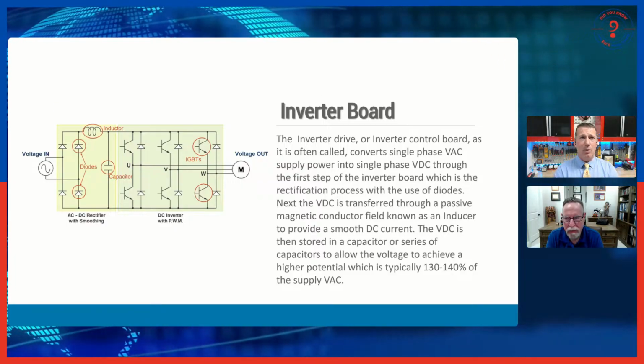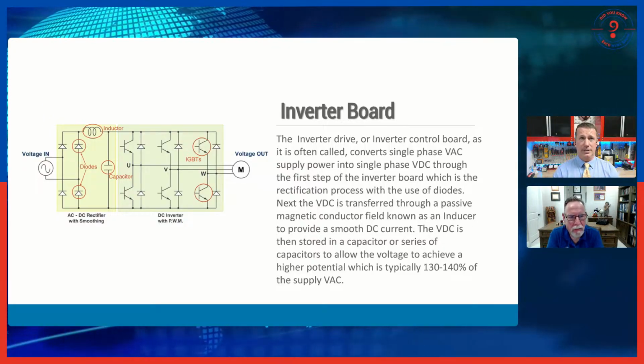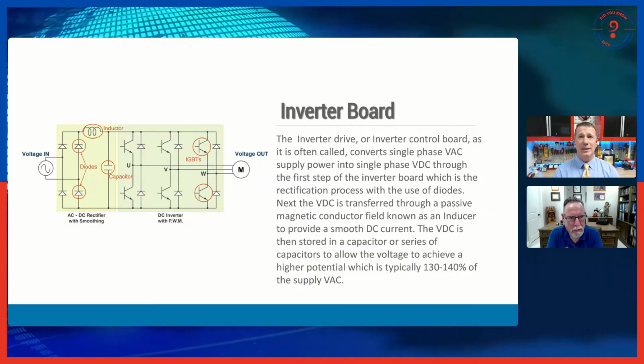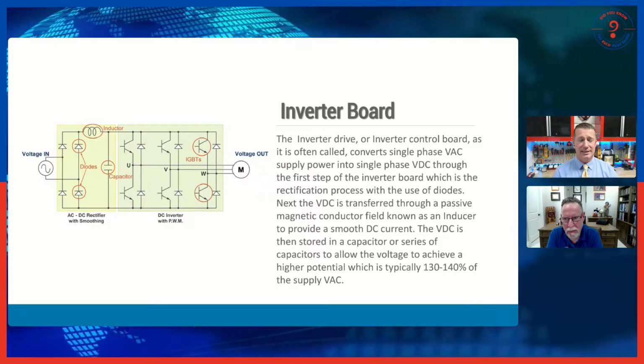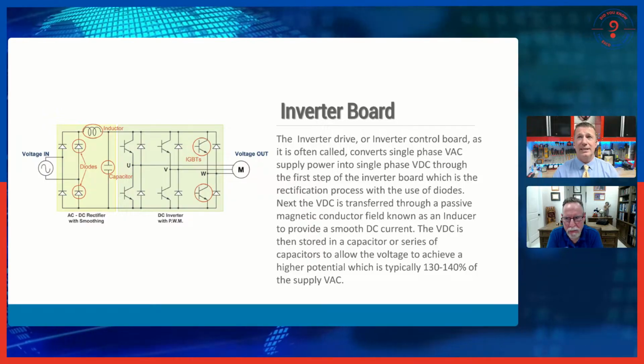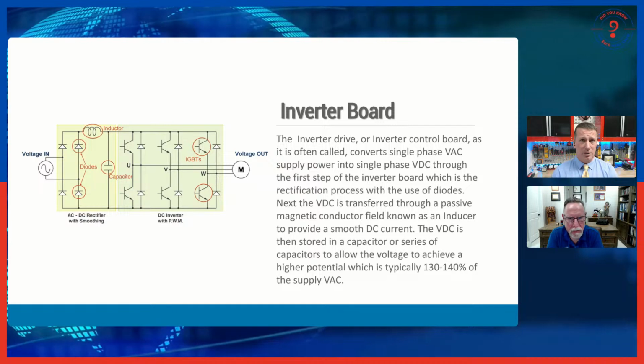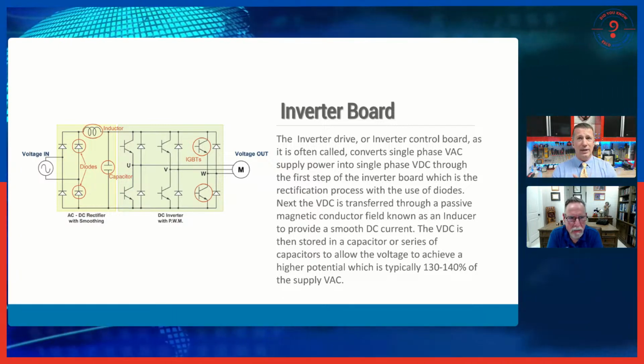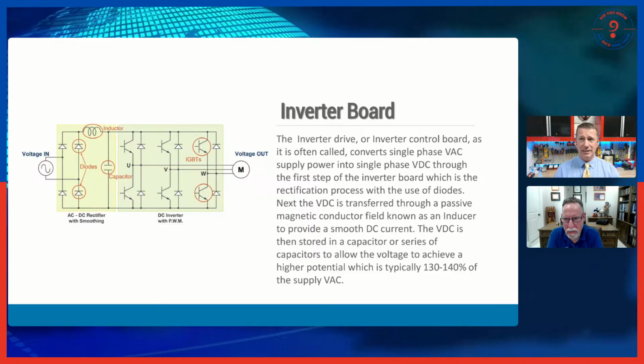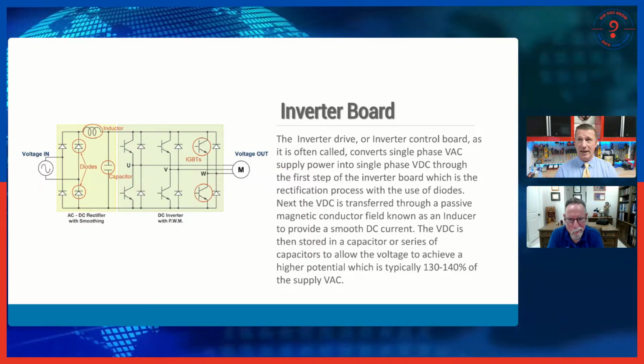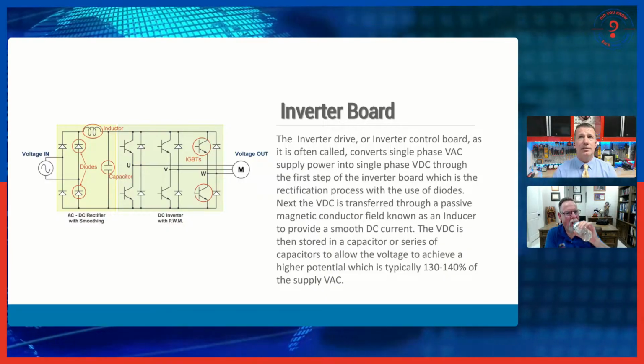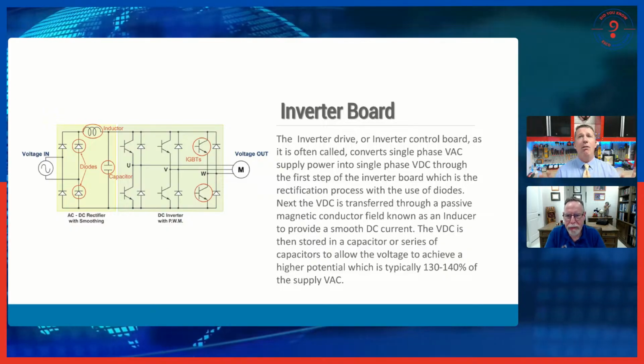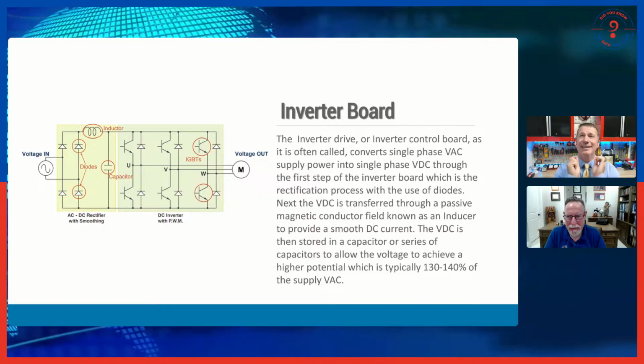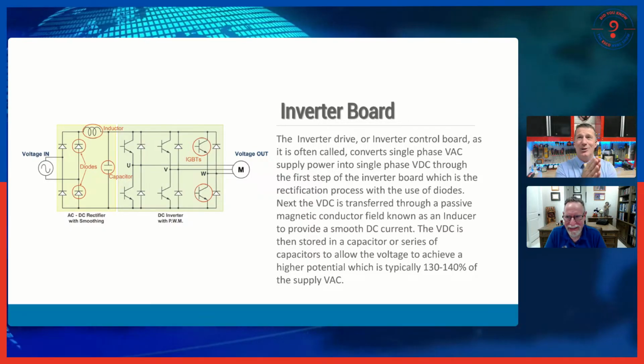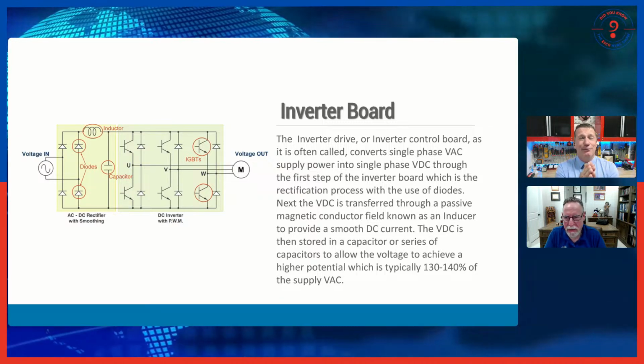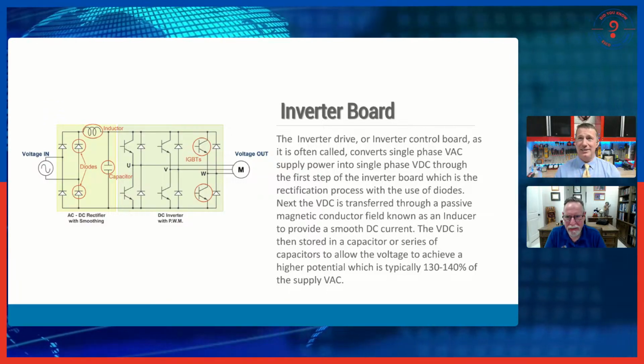We come in with our AC power, then convert that power into a DC voltage somewhere along the inverter process. Whether you're working on 120 volt AC, 240 volt AC, or 480 volt AC, what we store in DC is typically 130 to 140% of the incoming supply AC voltage. It's very common - if I've got 240 coming in on AC, I'll have approximately 300 volts DC stored at our capacitor banks. All manufacturers of inverter boards have test points for the DC voltage at the midpoint of the control: a place to test voltage coming in, a place to test voltage in the middle on our DC, and a place to check voltage on the output.